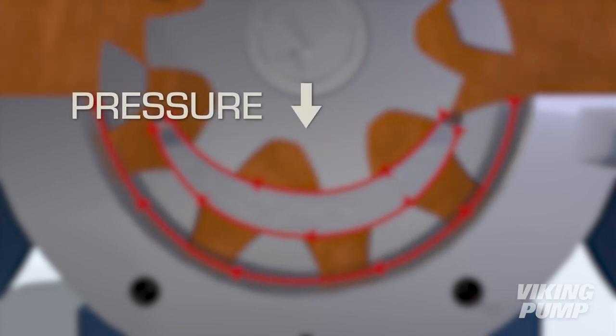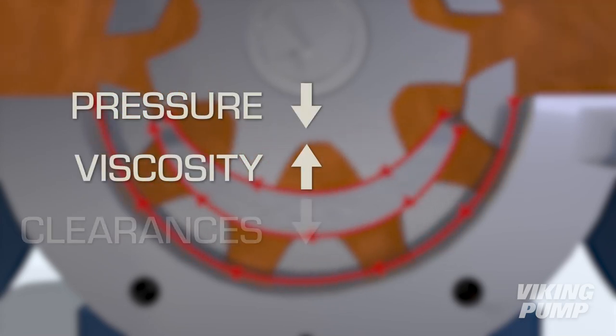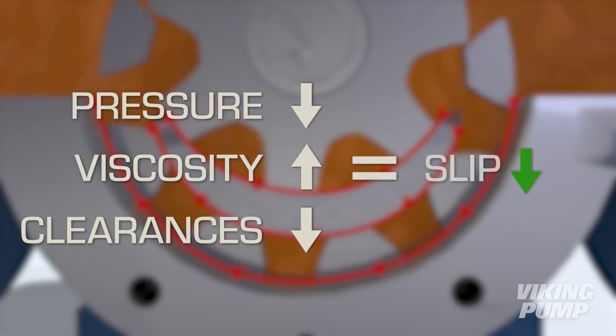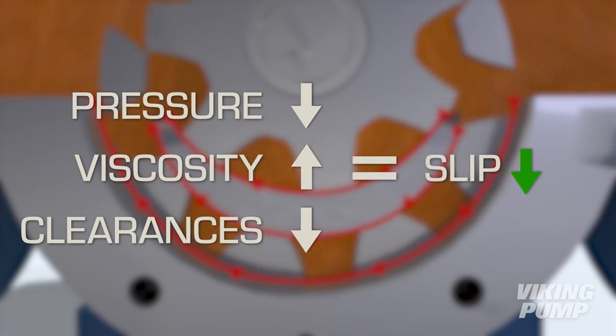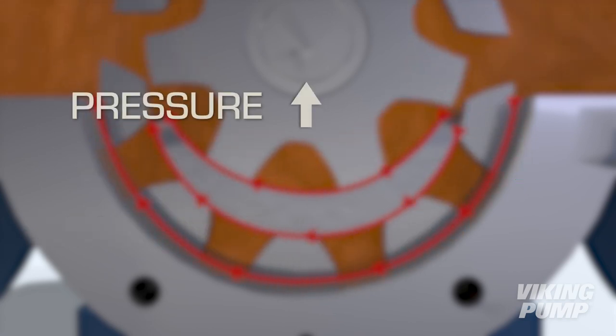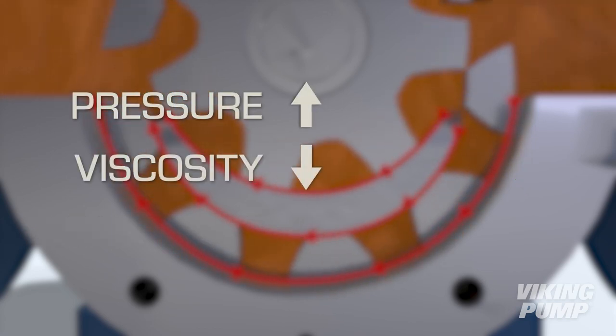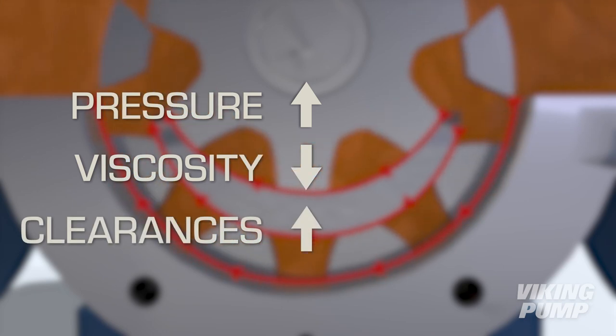If the pressure is low, viscosity is high, and clearances are tight, slip is low, and the actual flow is very close to the theoretical capacity of the pump. Conversely, when pressure is high, viscosity is low, and clearances are wide, the slip is high.